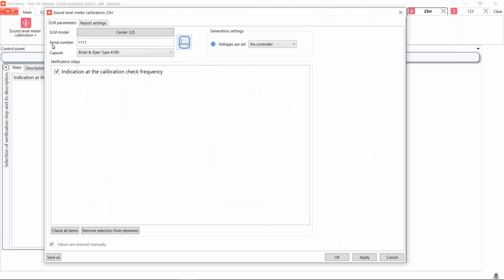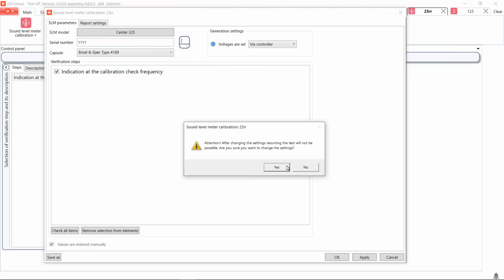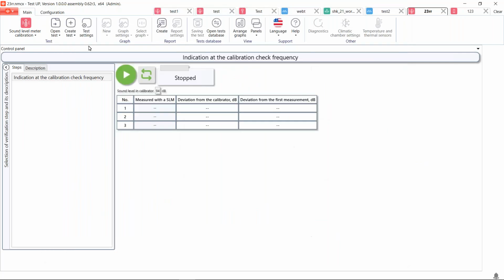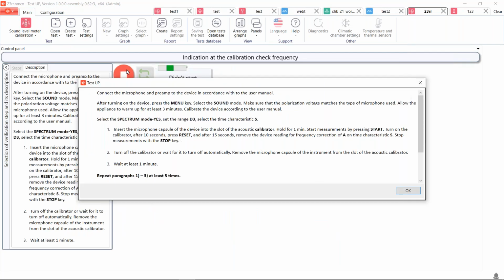We check that we put here the serial number, the capsule, the sound level meter model, of course, and now we can apply it and start our calibration procedure. So you can't see it at the moment, but what I'm doing is I put the microphone capsule of the device into the slot of the acoustic calibrator. So you can see the description of the procedure on your screen right now, and I am performing it in our lab.